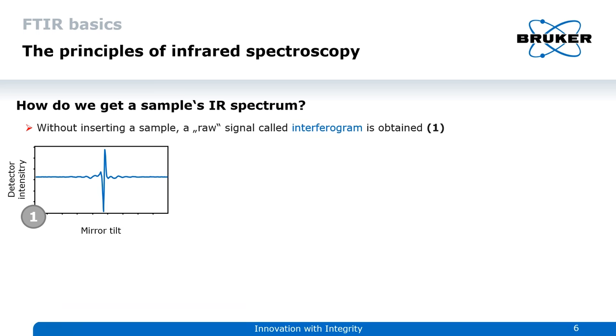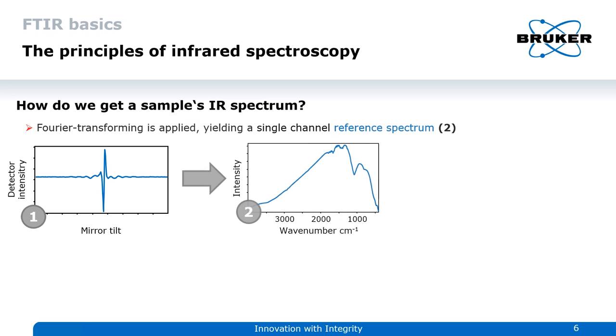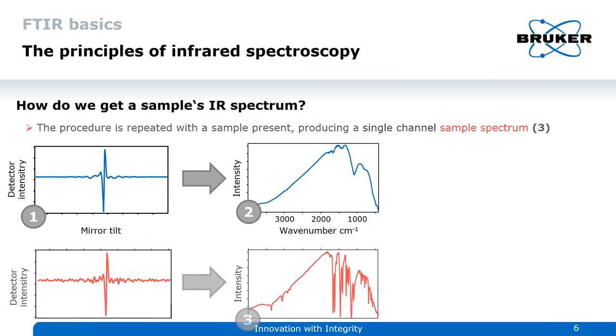This raw signal is then mathematically Fourier transformed into the classical IR plot of light intensity versus wavenumbers. We now have a single-channel reference spectrum. Then we insert the sample into the beam path and repeat the procedure. Fourier transformation then yields another single channel.